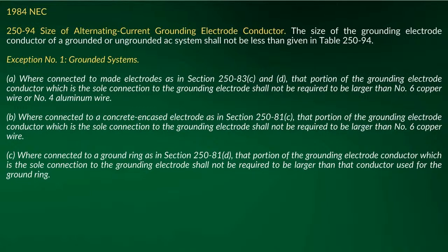Now we go to the 1984, and look what we start seeing. We get something different here. Okay? You're going to see they're going to have 250-83C and D, which we just looked at. Then they come in and they hit 250.81C, where they talk about to the concrete encased electrode, and then 250.81D as you go to a ground ring. And at this point, we still are calling the ground rod and pipe and plate a made electrode. Do you see that? Yep. Okay. So this way, nobody can say I'm making anything up here. I'm showing you exactly the wording that was in the code at the time.